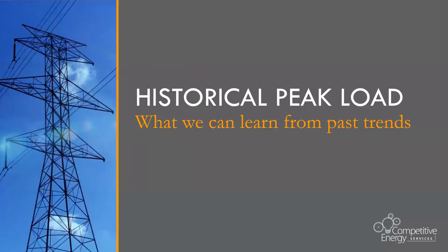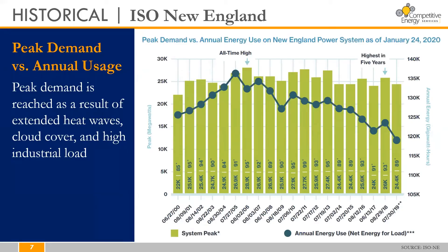Next, let's take a look at historical ISO New England peak load. This graph from ISO New England shows peak demand versus annual electricity usage for the past 20 years. Peak demand — the day and hour which represents the system peak — is shown by the lime green bar graph, while annual electricity usage for the whole ISO New England grid is shown by the dark green line graph. The x-axis shows which day of the year the peak occurred as well as the temperature on that day. Despite the decline in annual electricity usage in recent years, peak demand continues to stay within the range of 24 to 26,000 megawatts during the peak hour. The purpose of this graph is to highlight that there are no clear correlations between total annual electricity usage and peak grid demand — demand and usage are two separate concepts.